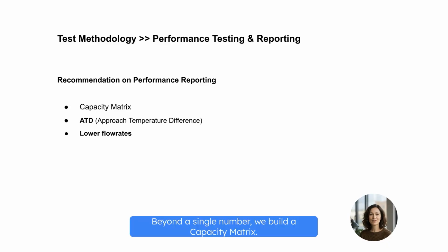Beyond a single number, we build a capacity matrix. This maps ATD, approach temperature difference, against flow rate variables. This is where design wins happen. If you can optimize your cold plates to run at lower flow rates or achieve a tighter ATD closer to 5 degrees, you are effectively unlocking free cooling capacity from the same CDU hardware.